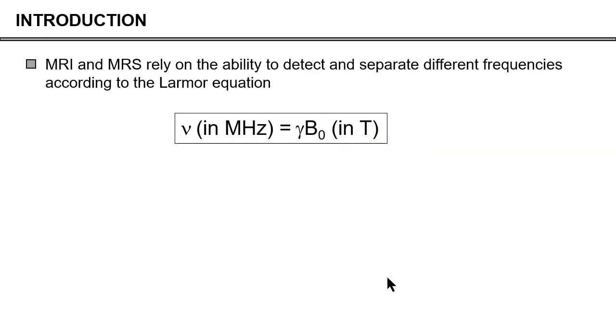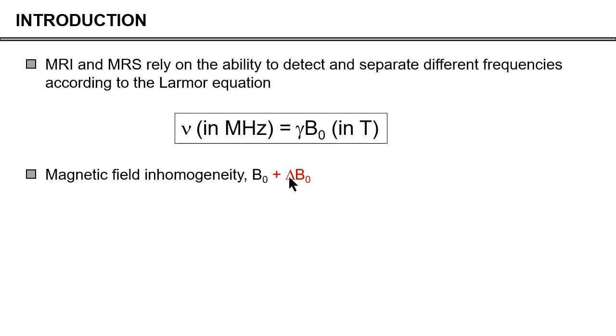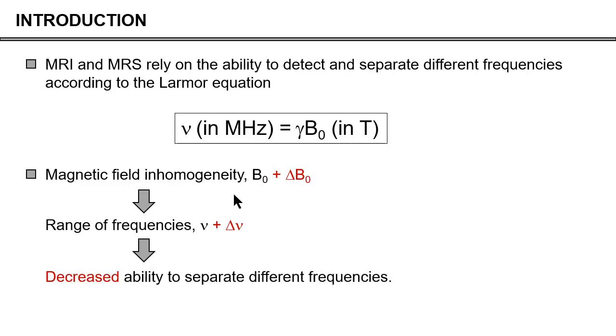Most people in the audience know that MRI and MRS — almost all aspects of it — rely on the ability to detect and especially separate different frequencies according to the Larmor equation, which says that the frequency you get, your Larmor frequency, is proportional to the magnetic field in Tesla. This simple equation also means that if you have an inhomogeneity in your main magnetic field, delta B0, that automatically introduces a range of frequencies, and therefore decreases your ability to separate those frequencies. And that is a bad thing for both MRI and MRS.